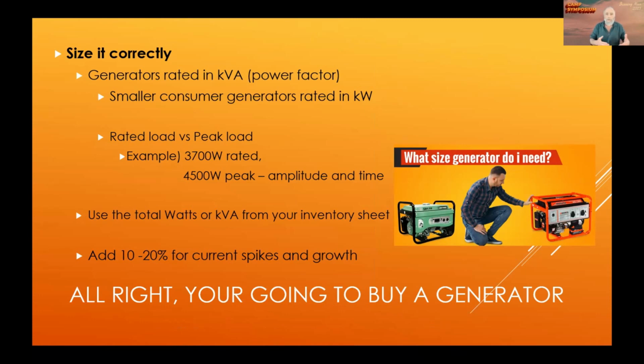But the smaller consumer generators are going to be rated in kilowatts. And that's for the ease of the consumer to figure out and compare generators. Generators are going to have a rated load and a peak load. You run in the rated load zone. Here we have an example of 3,700 watts. That's where the generator is going to do its running. Peak is when you have spikes of current from starting up equipment, motors, that sort of stuff. And in the peak mode, you don't run there. It'll accept peaks up to a certain amount of time. There's a time base and an amplitude to that peak, all the way up to 4,500 watts in this example.